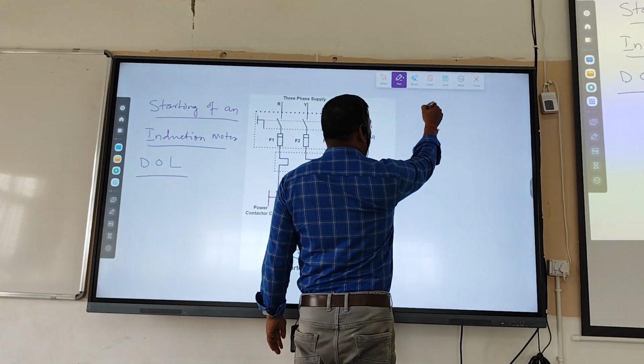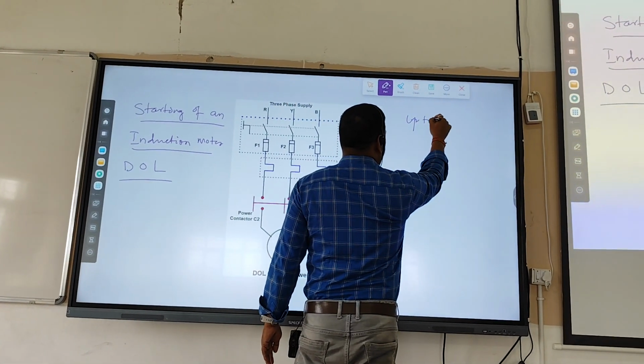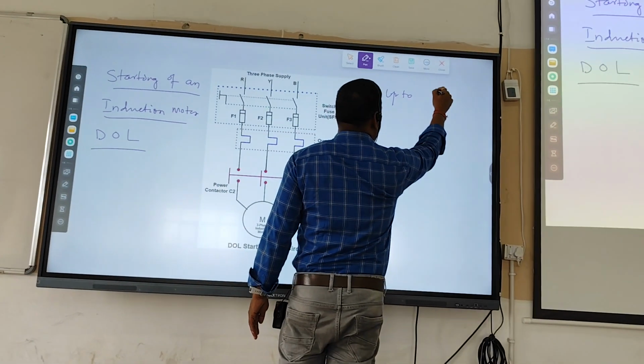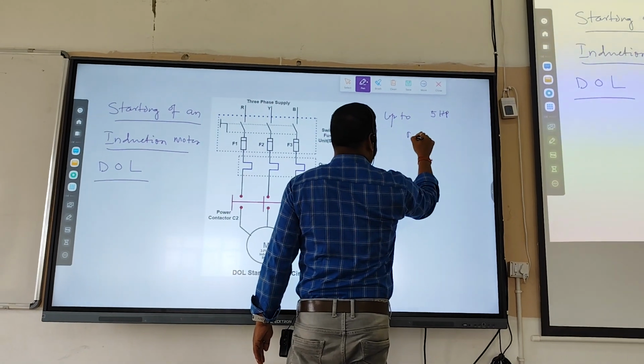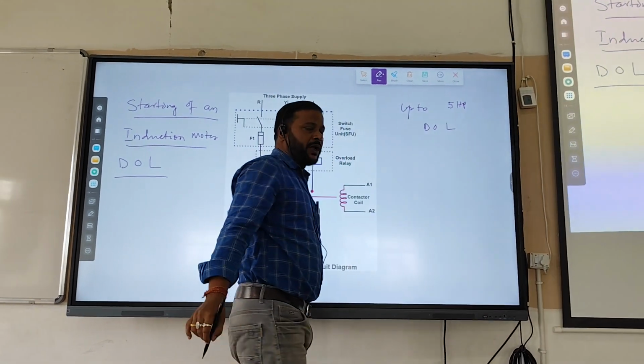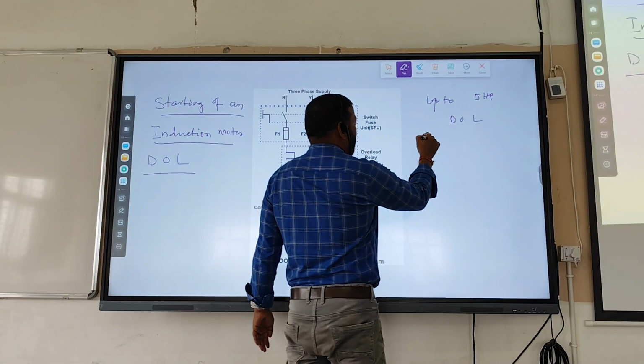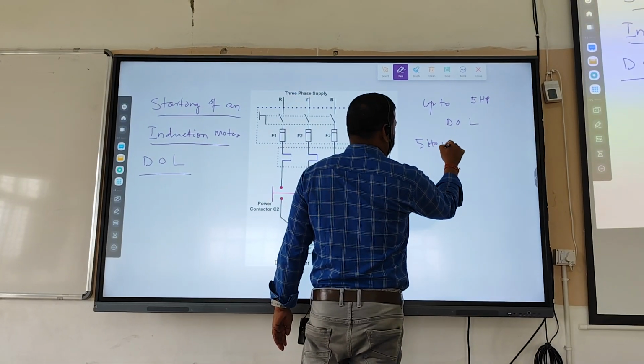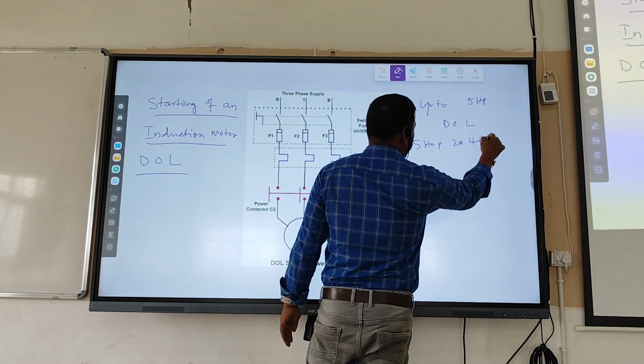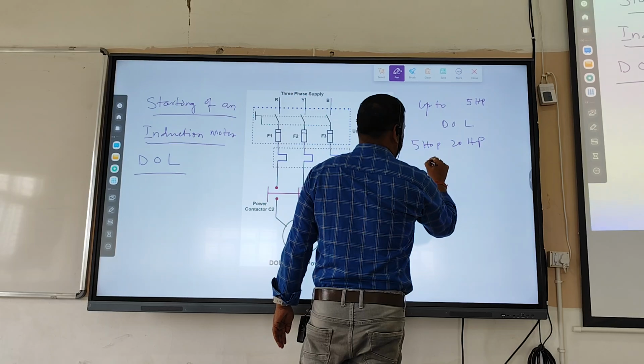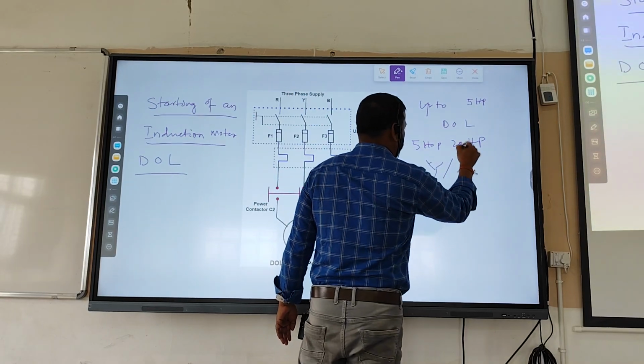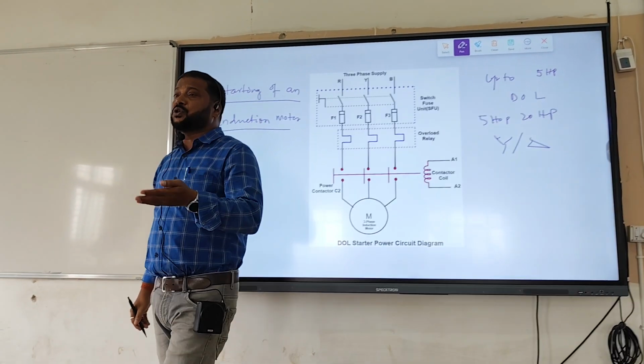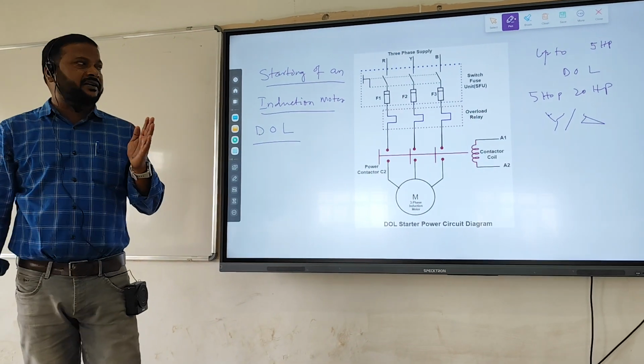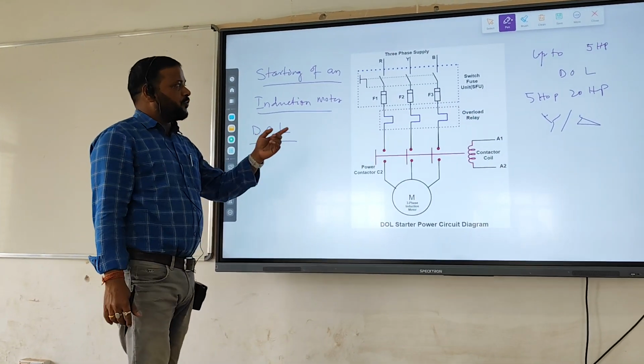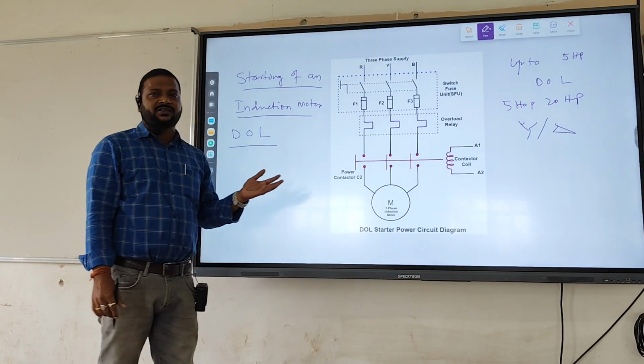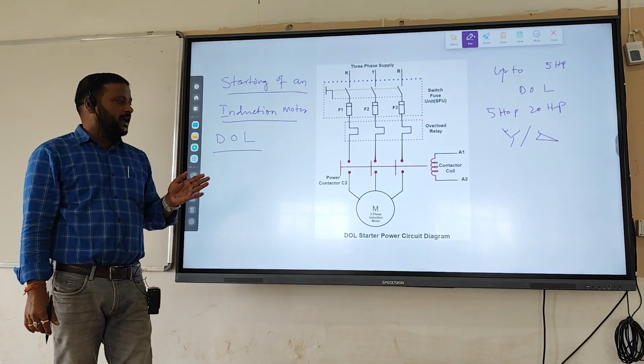Up to 5 HP, DOL starter is normally recommended. Above 5 HP up to 20 HP, star delta starter is recommended, and from 20 HP onwards, auto transformer starter is recommended. So today we will be having our discussion on the DOL starter, that is, direct online starter.